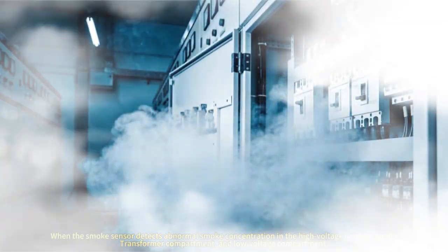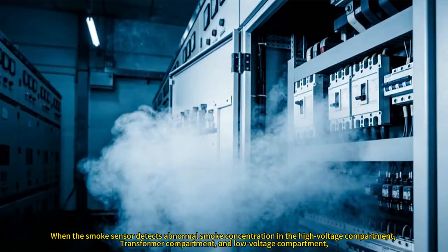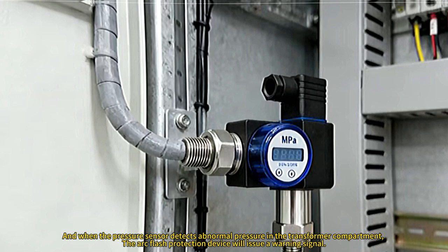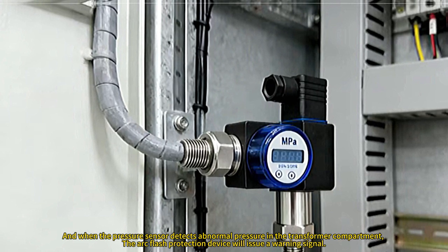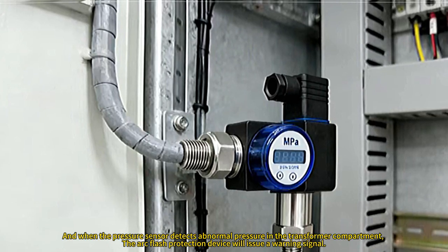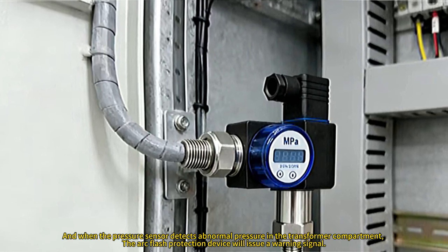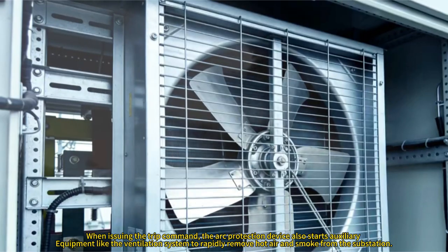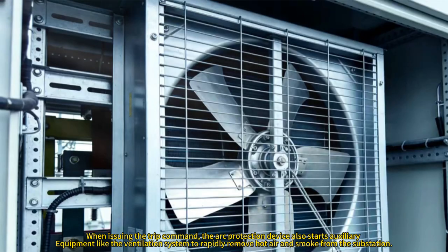When the smoke sensor detects abnormal smoke concentration in the high voltage compartment, transformer compartment, and low voltage compartment, and when the pressure sensor detects abnormal pressure in the transformer compartment, the arc flash protection device will issue a warning signal. When issuing the trip command, the arc protection device also starts auxiliary equipment like the ventilation system to rapidly remove hot air and smoke from the substation.